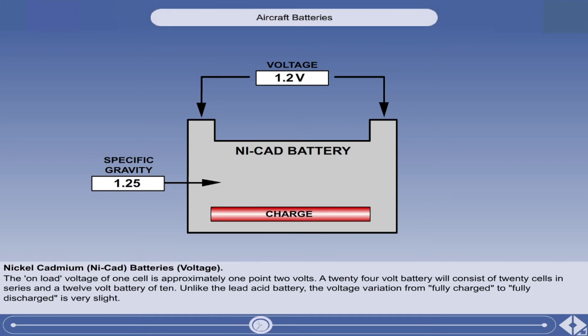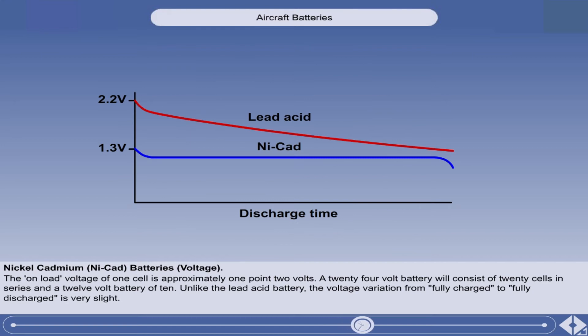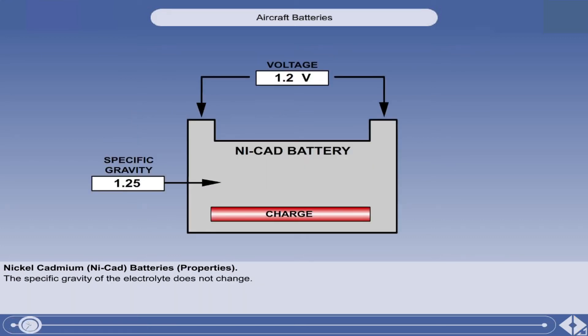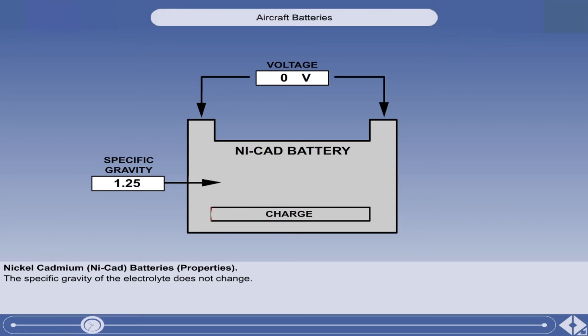A 24-volt battery will consist of 20 cells in series, and a 12-volt battery of 10. Unlike the lead acid battery, the voltage variation from fully charged to fully discharged is very slight. Here is a graphical representation of a comparison of a lead acid battery against that of a NICAD battery during discharge. As you can see, the NICAD battery holds a much more constant voltage during the discharge cycle. Unlike the lead acid battery, the specific gravity of the NICAD battery electrolyte does not change, and the voltage variation from fully charged to fully discharged is very slight.